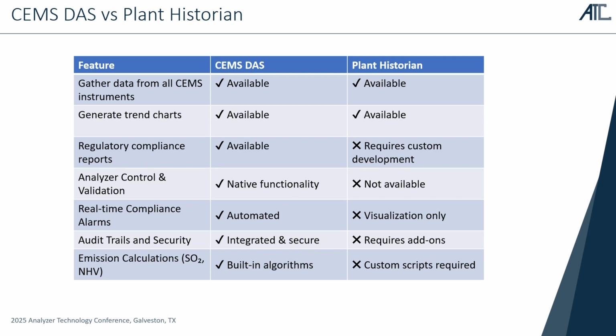The analyzer control and validation, one of the requirements usually for CEMS regulations is daily validation, and if the validation fails the threshold, then you need to calibrate. And again, multiplexing as well, when we're talking about putting multiple streams in the gas analyzer. So plant historians typically don't do that. You would need some sort of a PLC or a custom DAS system that can accomplish that.